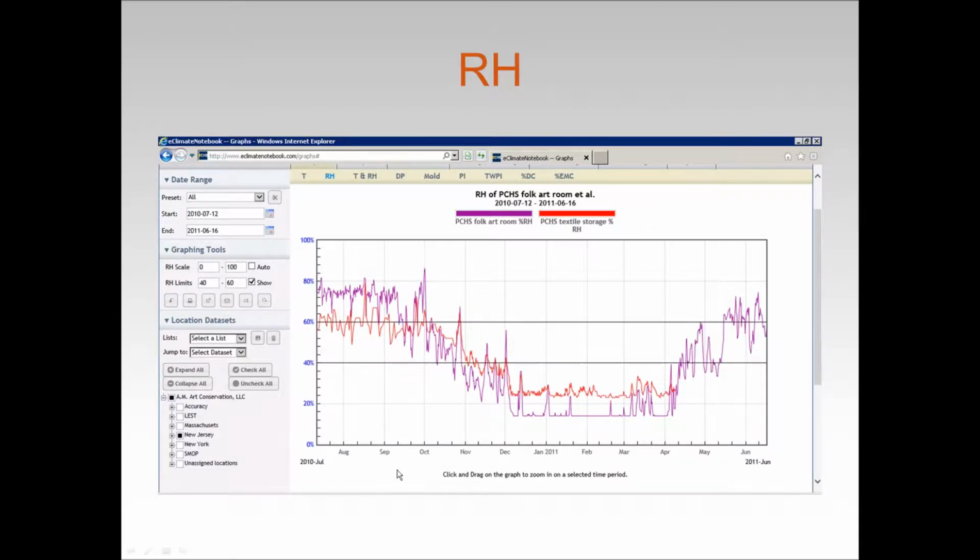I wanted to show you this graph because it was created by importing data from a different kind of logger, not a PM2. When this institution took a look at their data, they said, oh, this isn't so bad. We only dropped under 20% RH for a short period of time. But what I pointed out was that the other logger actually stopped measuring.